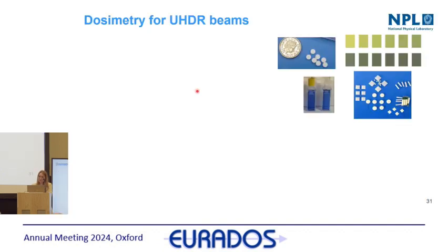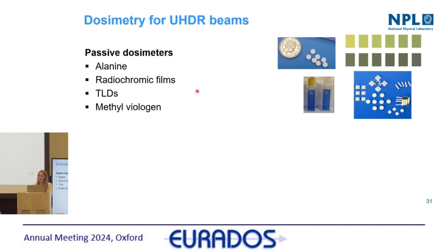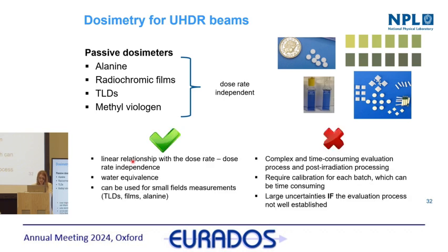I want to be a bit more complete and also mention that passive detectors are still very adequate devices for ultra-high dose rate exposure, especially the ones I've listed here, due to the fact that they are dose rate and dose per pulse independent. And in fact, those detectors have been probably the most widely cited in radiobiological literature, which is demonstrating that they carried out traceable dosimetry.